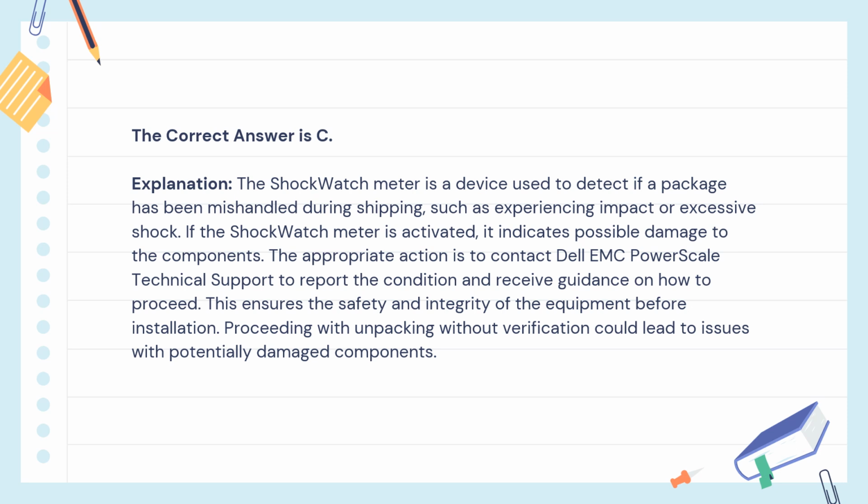Because the shock watch meter is a device used to detect if a package has been mishandled during shipping, such as experiencing impact or excessive shock. If the shock watch meter is activated, it indicates possible damage to the components. The appropriate action is to contact Dell EMC PowerScale technical support to report the condition and receive guidance on how to proceed. This ensures the safety and integrity of the equipment before installation. Proceeding with unpacking without verification could lead to issues with potentially damaged components.